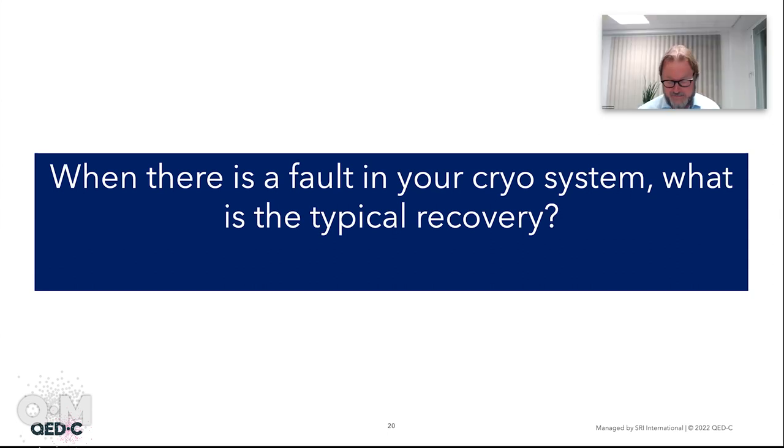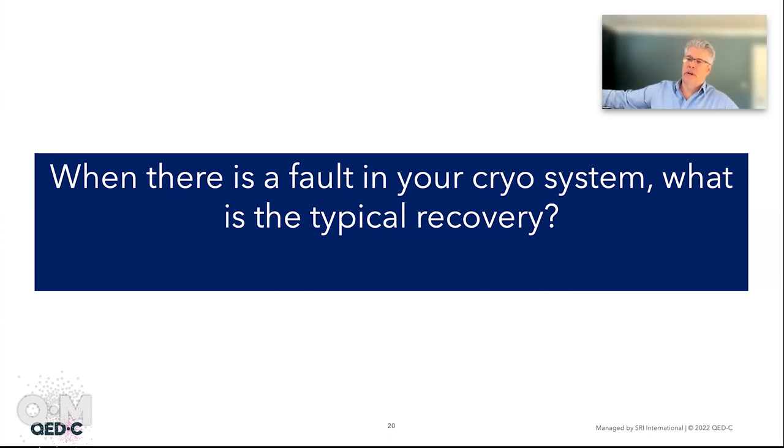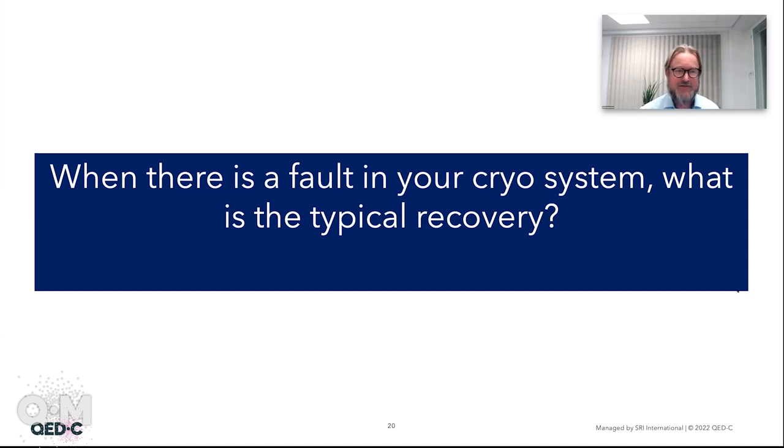And of course, the pulse tube itself, which is a quite critical part in our systems, as Arifin said, has quite good reliability. And if there is a fault in them, it's usually very slow. So you can keep on running and do planned maintenance. As he said, you can watch its performance start to degrade, so you know something's happening and can plan for that event, right? Yes. But of course, the more stuff the user puts in this system, if there is a failure where it actually has to warm up, it is a long overhaul. But there is a lot customers can do to avoid that: maintenance is one thing, and making sure that redundancies are there. In the best case, they should have two computers running in parallel.